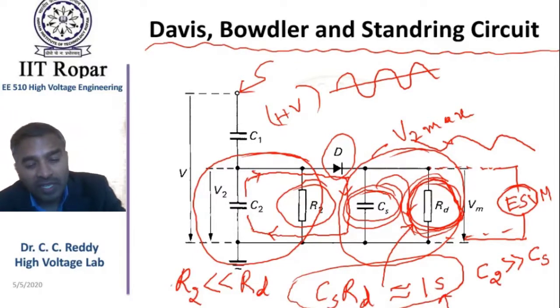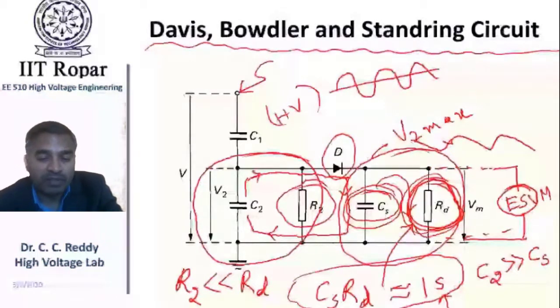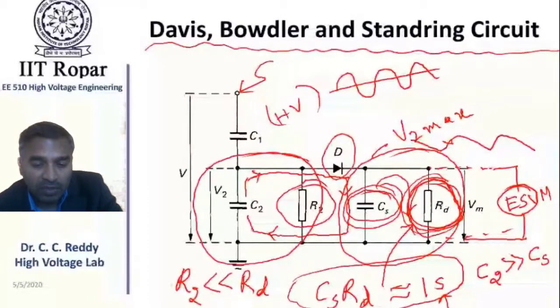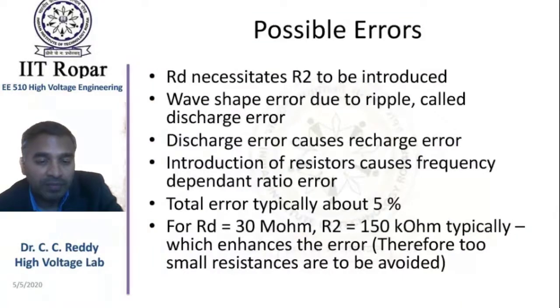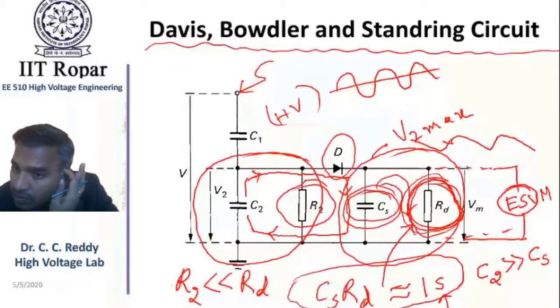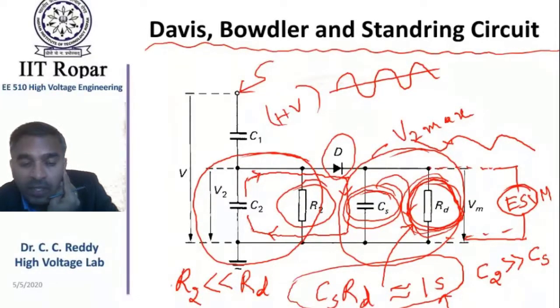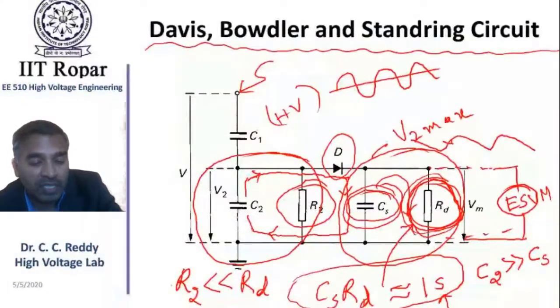But if RD is introduced, or if R2 is introduced, since it is parallel to C2, it is not pure imaginary impedance anymore but complex impedance. Therefore, frequency dependence comes into the divider ratio. So these are all the possible sources of error with this kind of circuit. Then that will lead to harmonics also, no sir? If there is frequency dependency, harmonics also come into play, and the ratio changes with harmonics too. So that is the difficulty of this circuit.